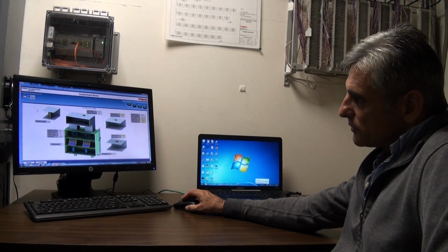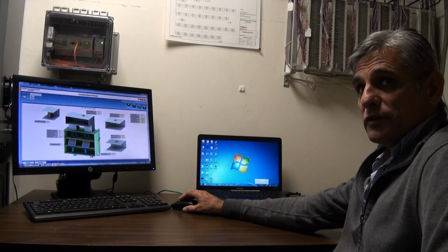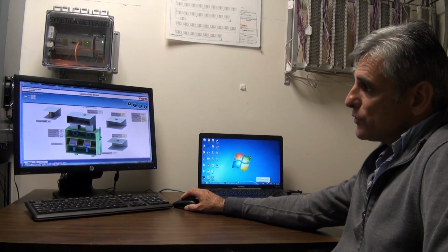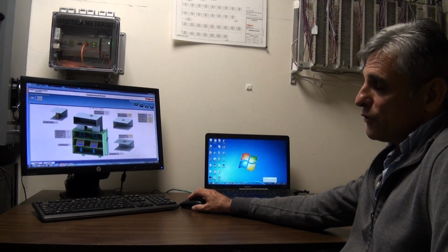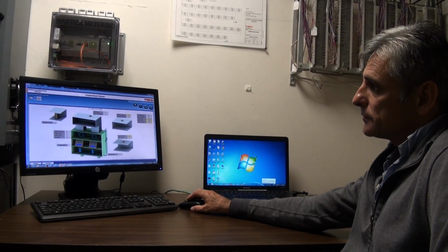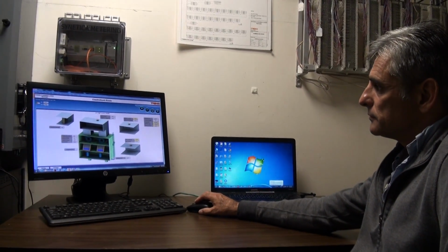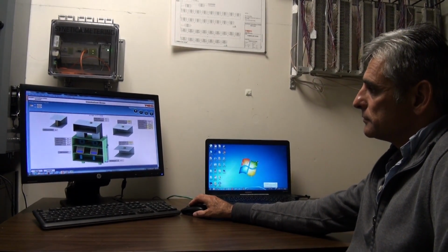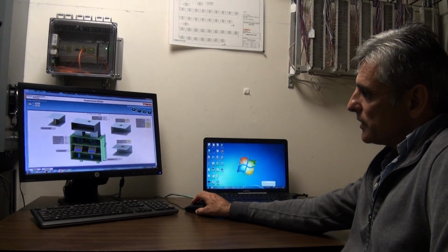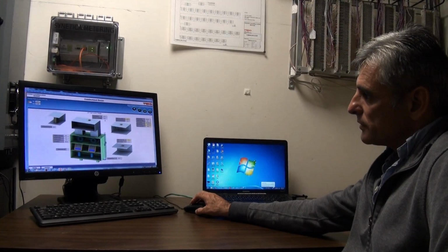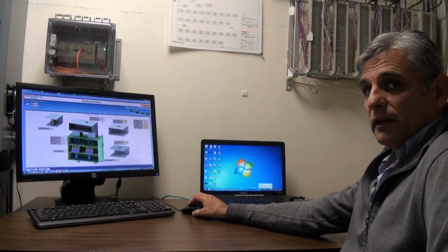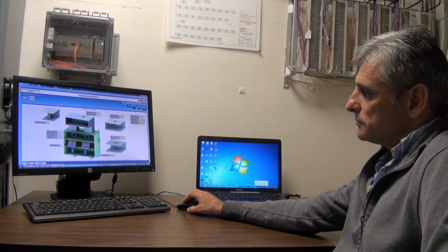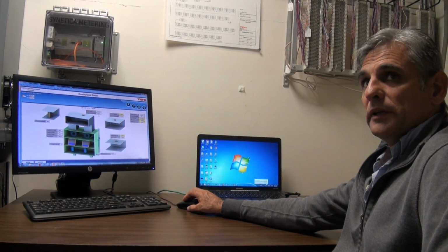Also in these graphics, we're monitoring the current outside air temperature, and we're monitoring the current outside air humidity. As you see, this temperature's dropped slightly. It's a very slow process because we don't want to shock the building.